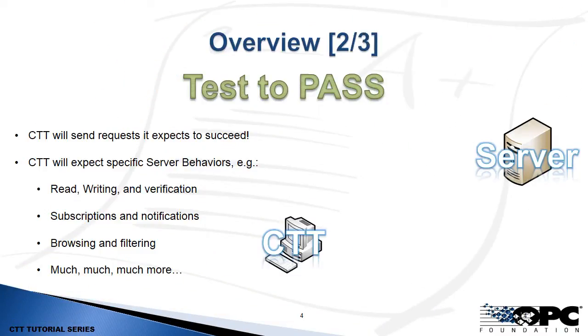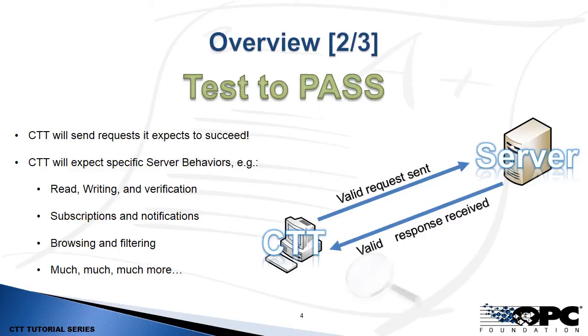What does it mean when we talk about tests to pass? The CTT will send specific instructions to the server because it's expecting certain behaviors — perhaps we're doing a read, write, or setting up a subscription — and then when the server responds, the CTT is checking those responses to make sure they match the expectations it's programmed with. These tests occur for all UA behaviors: reading, writing, subscriptions, browsing, events, etc.